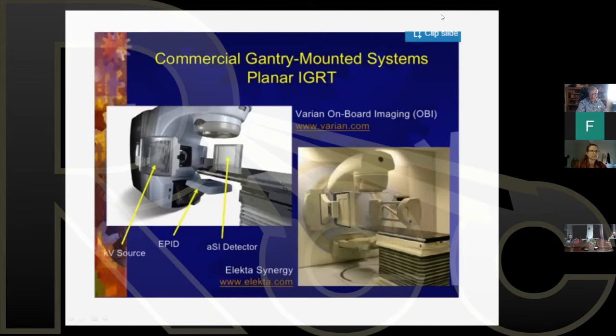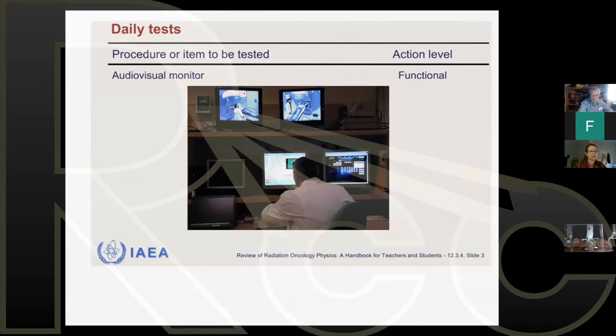Here's an example of two very common machines, the Varian machine on the left and the Elekta machine on the right. And both machines have the ability to take portal imaging with the megavoltage beam here and here, or using an X-ray tube KV imaging at 90 degrees to the MV imaging. Here's the X-ray tube on the Elekta machine. There's the imaging panel. These panels use an amorphous silicon detector. It's electronic imaging, no need to develop films. The images appear very quickly on a monitor, and the therapist can evaluate those images with software provided by the vendor. We'll talk more about that too.